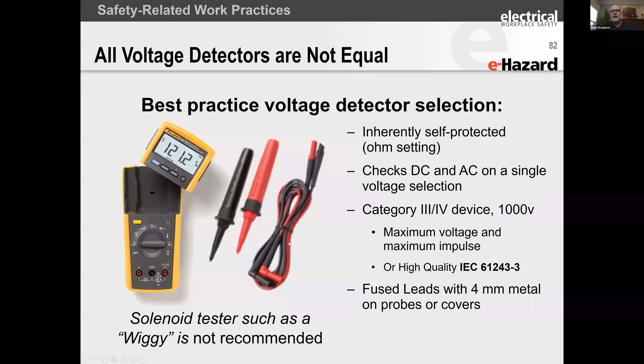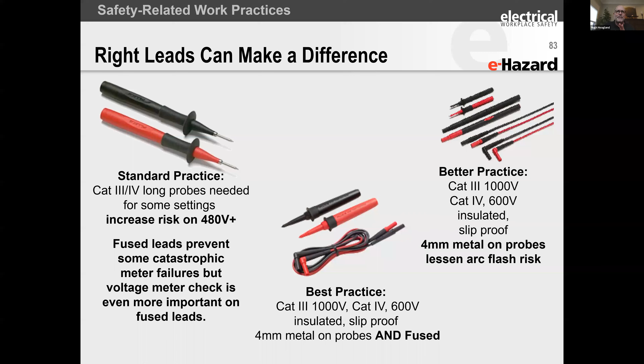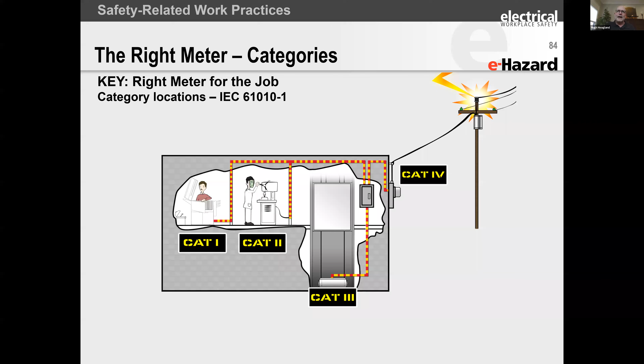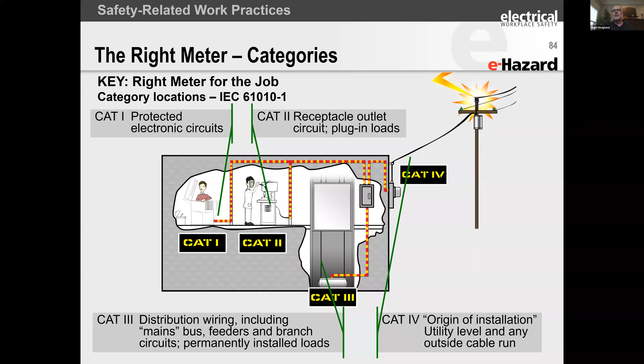And also probes, we recommend you go for very little metal on the probe so you can't cause an arc with the probe, and retractable probes, and if at all possible, fused probes. You can use those on the two-pole 61243-3, you can't use them on a 61010 because it's gotten more accurate for computer level voltage testing in milliamps. So now you can't use the fused probes or resistive probes, but they are safer on the higher voltage type systems if you accidentally get them in the wrong place. We used to recommend a Cat 3 or 4 meter, but if you're using the two-pole meters, they're not going to have those categories on them most of the time. And so those are the safest ones to use.